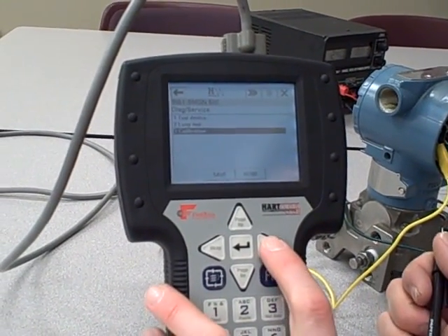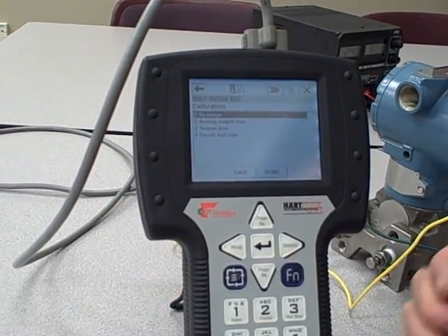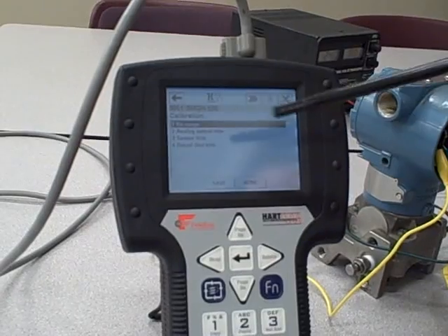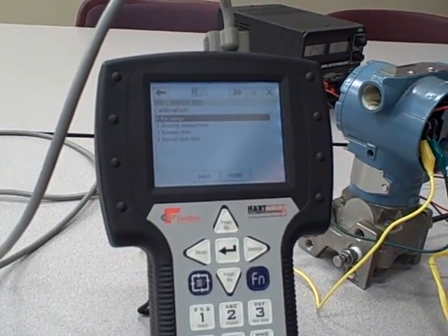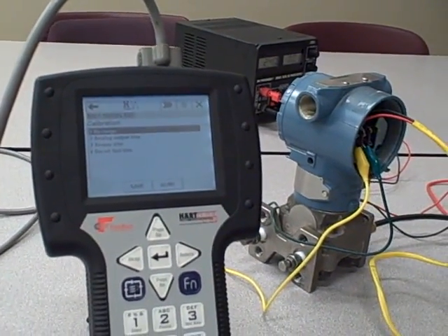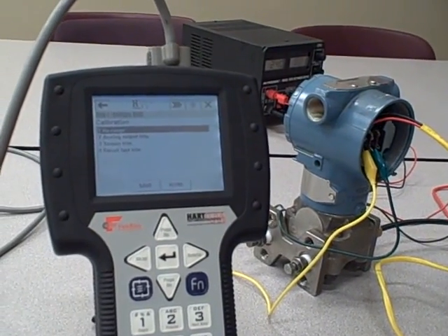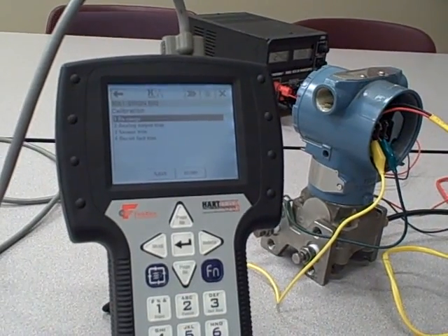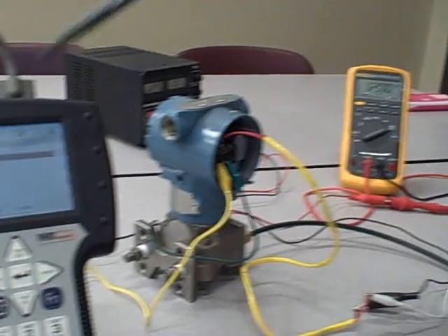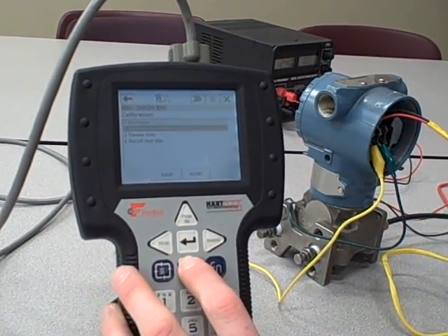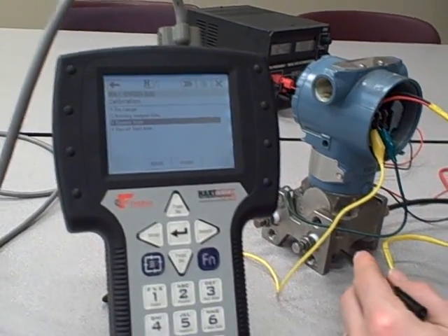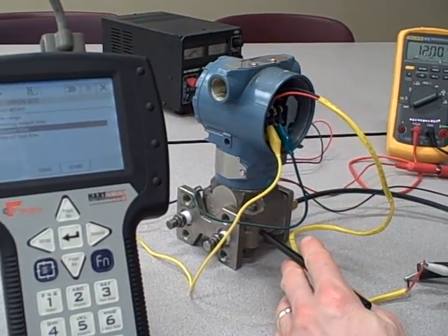Under calibration, this is a very important menu for instrument technicians. We can set the range points, which we could set from other screens too. We can do what's called an analog output trim, which tells or confirms to the transmitter what 4 and 20 milliamps looks like. For example, our last test, where we forced the output to go to 20 milliamps and our Fluke meter actually read 20.01, may indicate the need to do an analog output trim. We can also do a sensor trim, where we tell or confirm to the transmitter what certain amounts of pressure actually look like when applied to the cell.